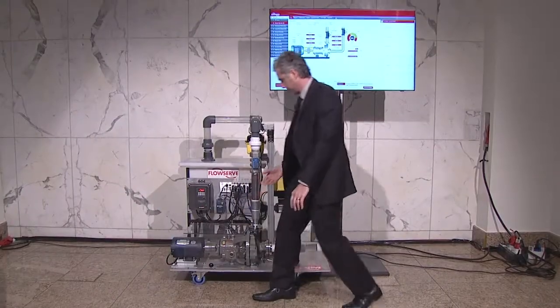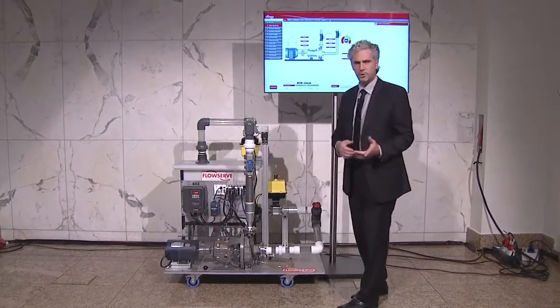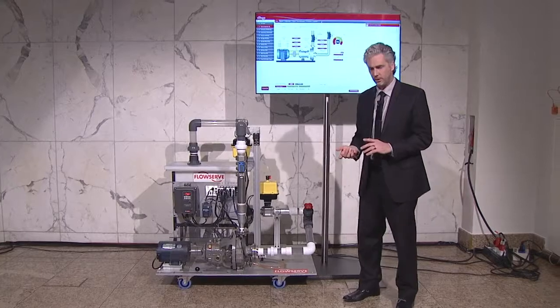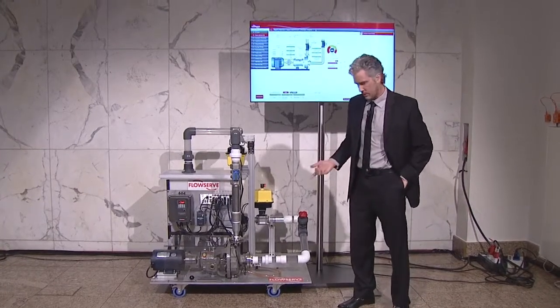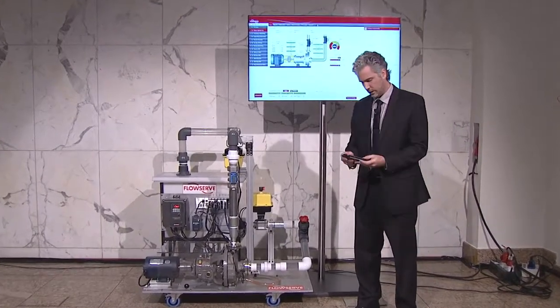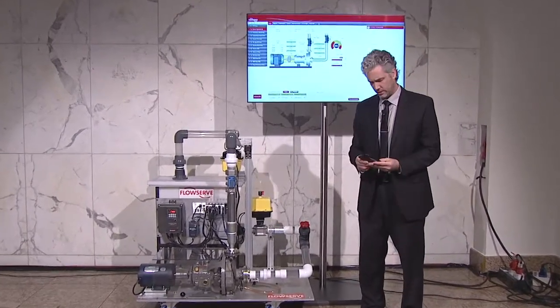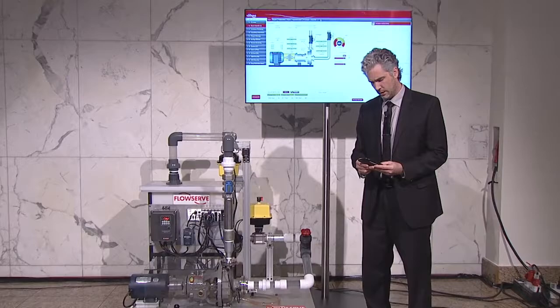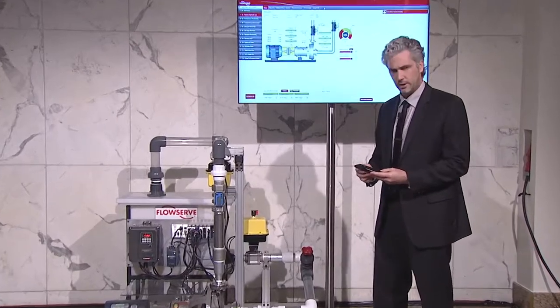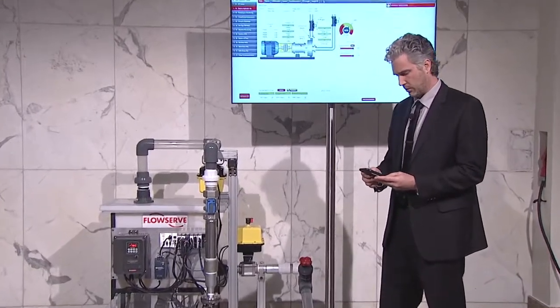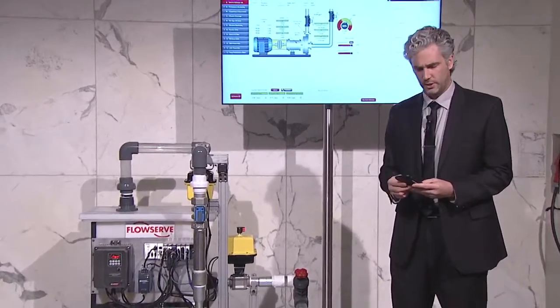What we've shown is that the pump is able to distinguish between two different types of failures. The pump is pretty smart — it sent me an email saying that it's going to have an impeller failure here in a couple of days.